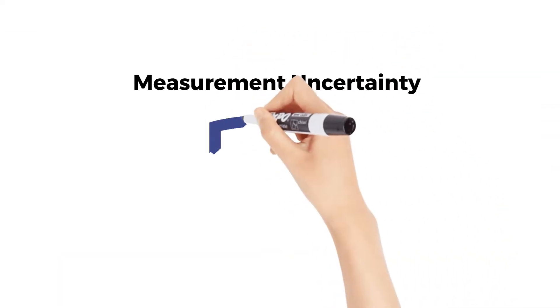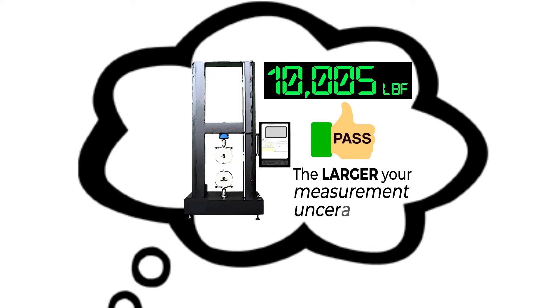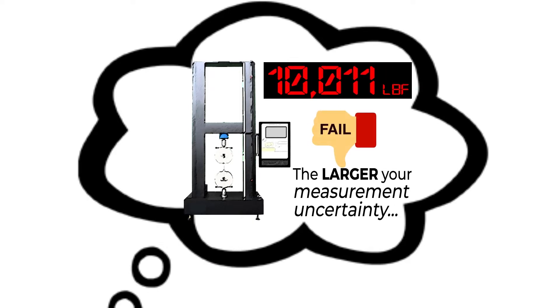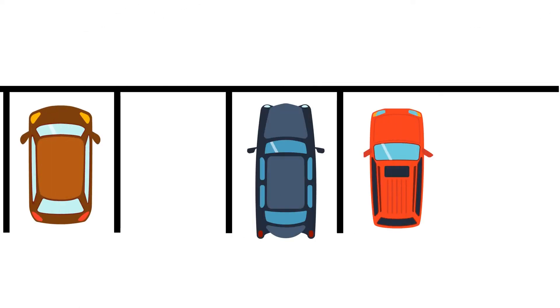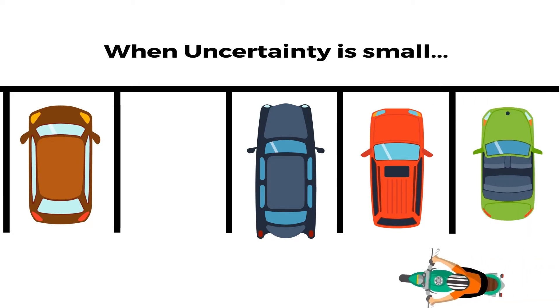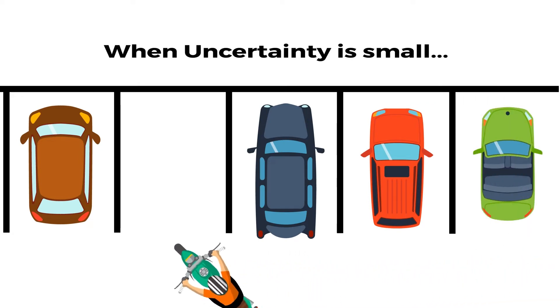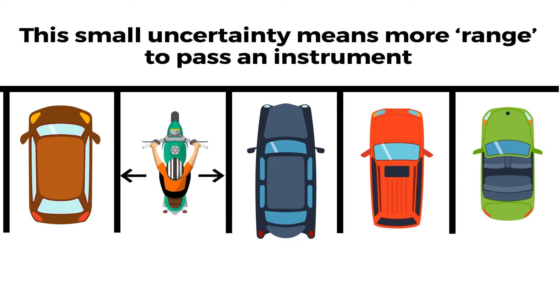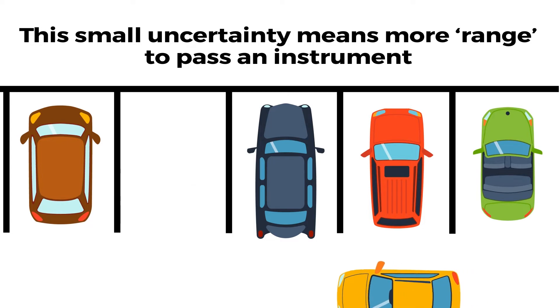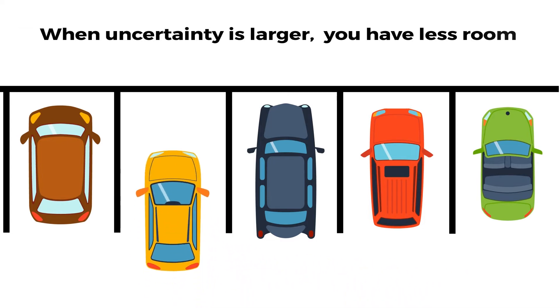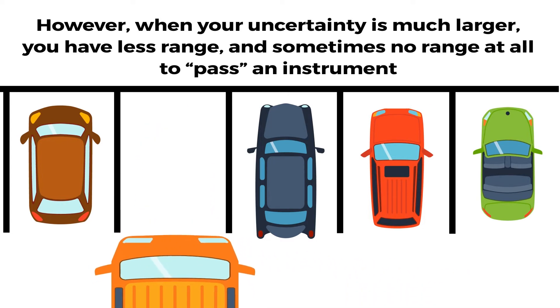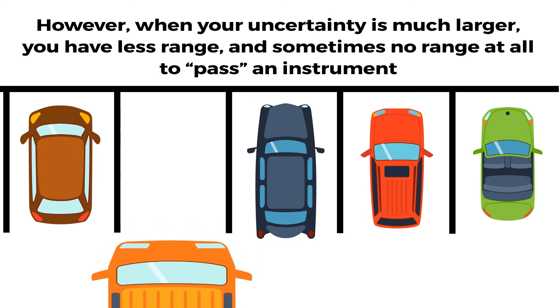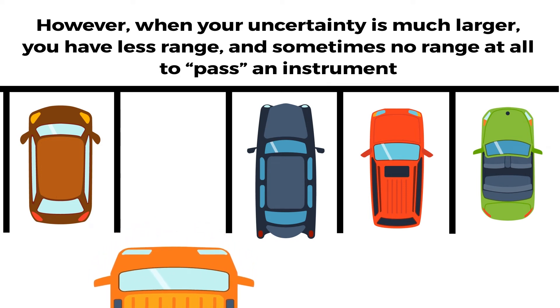Measurement uncertainty also keeps us honest. If we think about making a conformity assessment of pass or fail, the larger your measurement uncertainty, the more likely you are to fail an instrument. Using the analogy of a parking space, when your uncertainty is small, you have a parking space large enough to easily park — meaning more range to pass an instrument. However, when your uncertainty is larger, you have less room, and if the uncertainty is much larger, you have less range and sometimes no range at all to pass an instrument.